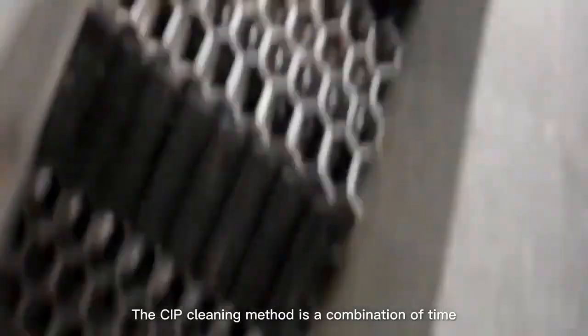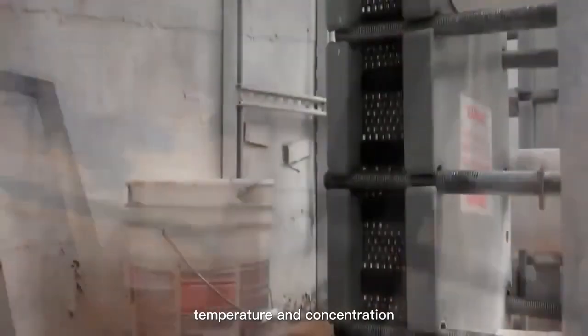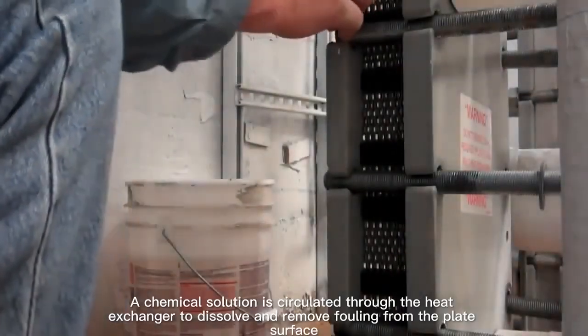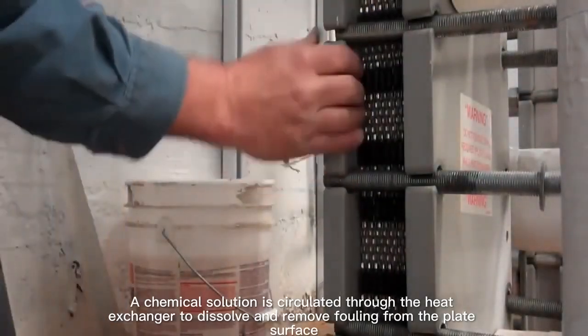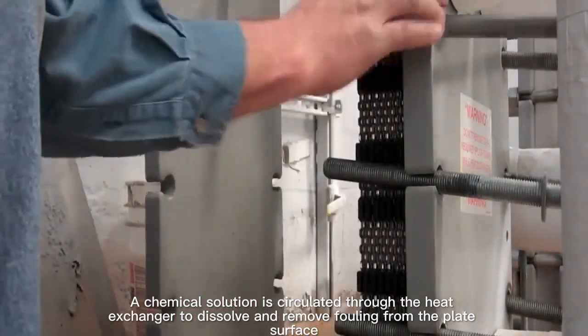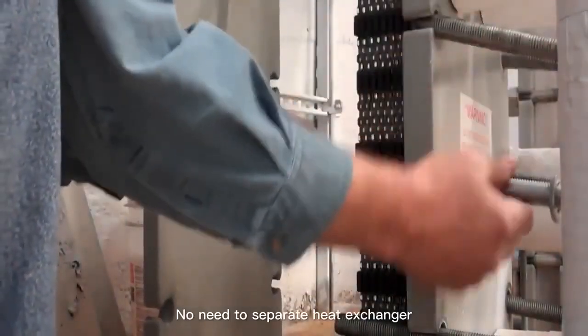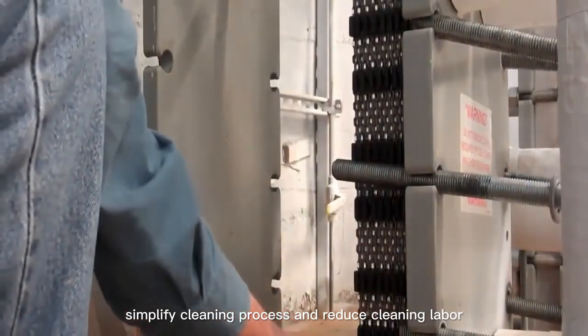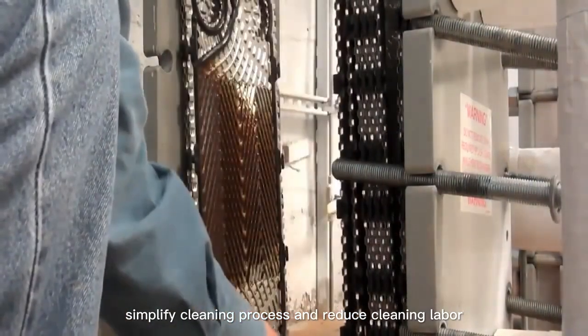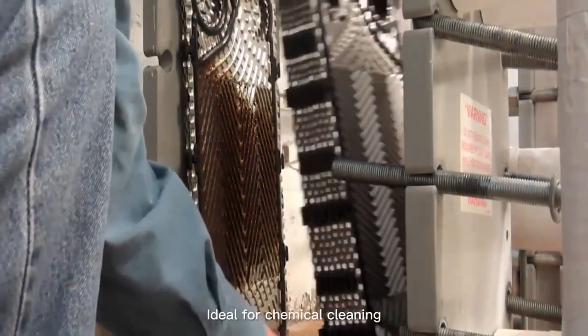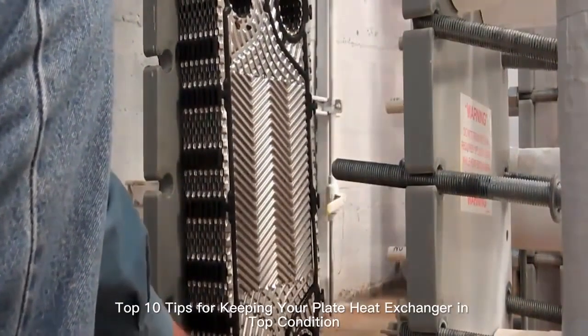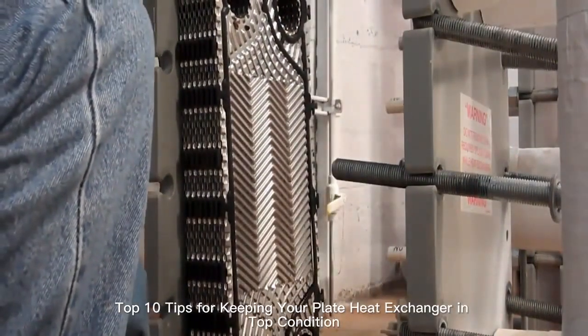CIP method of cleaning a plate heat exchanger. The CIP cleaning method is a combination of time, temperature, and concentration. A chemical solution is circulated through the heat exchanger to dissolve and remove fouling from the plate surface. There is no need to separate the heat exchanger, which simplifies the cleaning process and reduces cleaning labor. Ideal for chemical cleaning. Top 10 tips for keeping your plate heat exchanger in top condition.